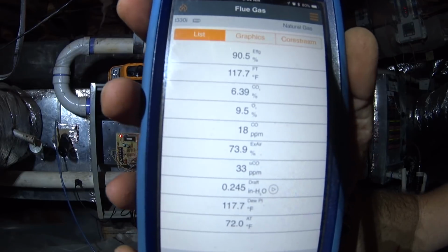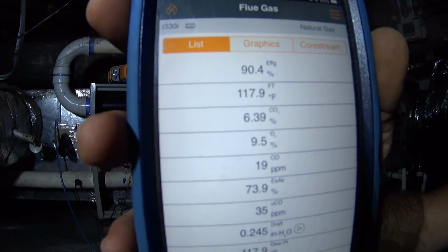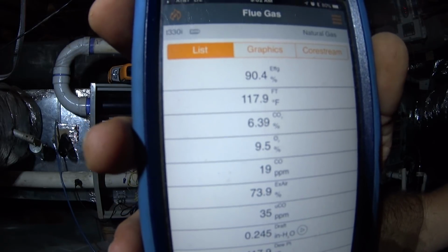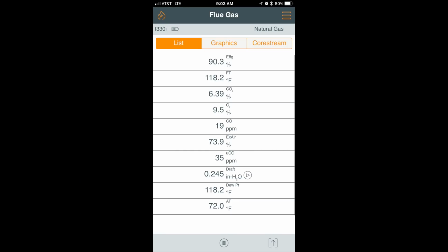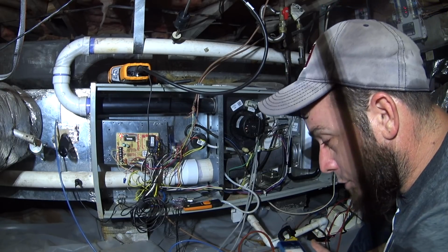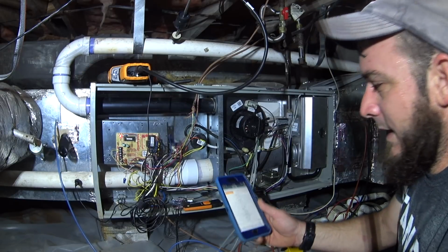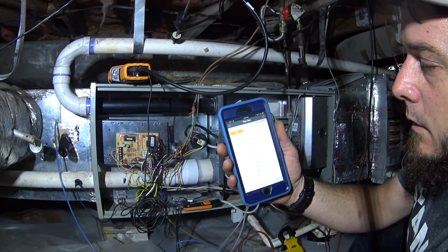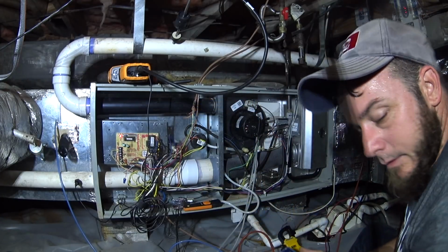The numbers as they are now for combustion are 90.4 percent efficient, 118 stack temperature, CO2 at 6.4, O2 at 9.5, CO PPM at 19, excess air is 73.9. We've got the system maxed out on the manufacturer's recommended gas pressure. So that's partly why we're not getting a better excess air number.